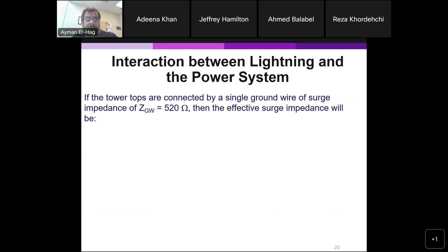Okay, now if the tower tops are connected to a single ground wire, so we have a tower here, and this tower has only one single ground wire, and this has an impedance equal to 520 ohms. So this tower has 500. And then something hits. Now, the reason we have this ground wire is that it's the tallest point, so the probability that a lightning strike hits it rather than the line is much higher. So whenever lightning hits, especially within the shield angle, if the lightning hits that wire, what will happen?